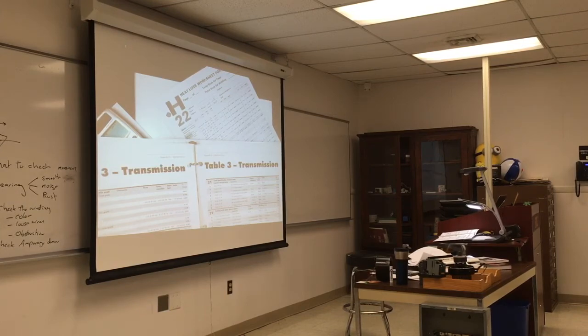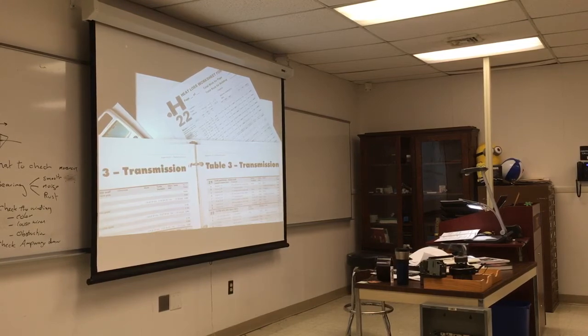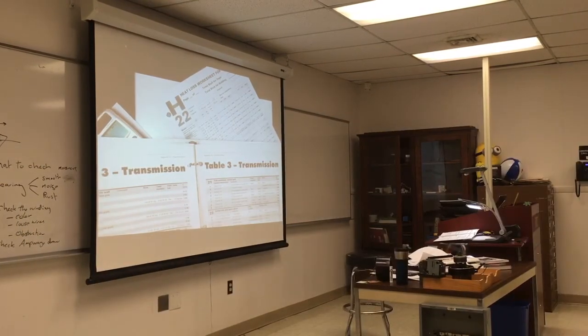We're going to consider the whole thing as the outdoor temperature. 1360, I rounded up to 1360. What did you use for a floor? We wrote it down, I have 0.05 for the floor table. What do you have for wall on your list? In the project, table 3, section 13H, U factor is 0.29. We used 0.112, right? Because it's got windows.